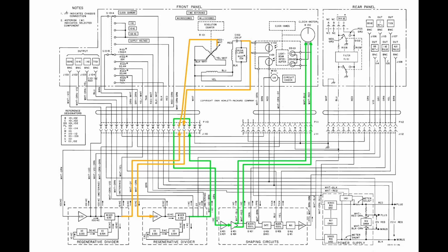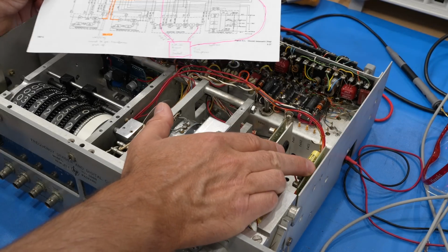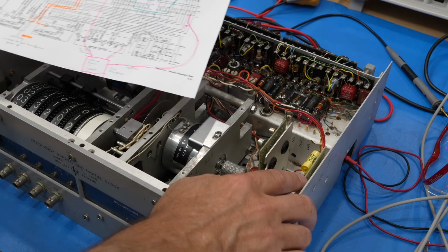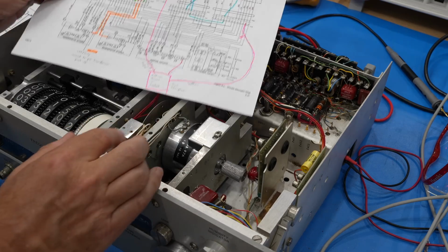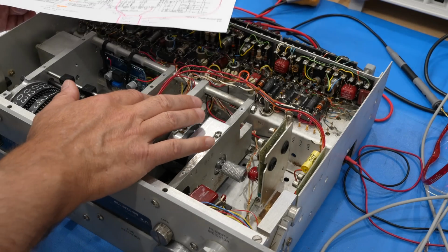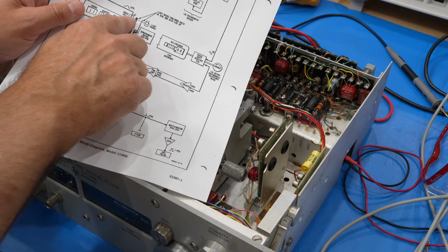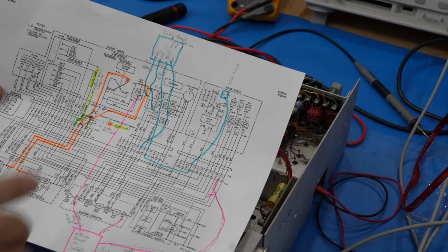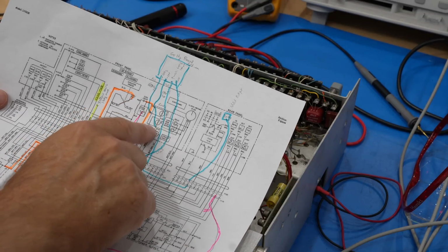It's all starting to make sense, but what about the 2 additional boards? What do these do? And then there are 2 cards. So I first reverse engineered the one over here. It turns out it's yet another modification. This instrument has not 1 photocell but 2 photocells. So the 2 photocells, they appear here, but one is not connected to anything.